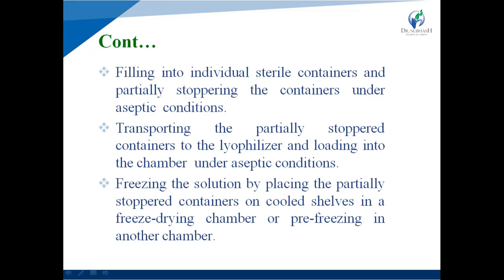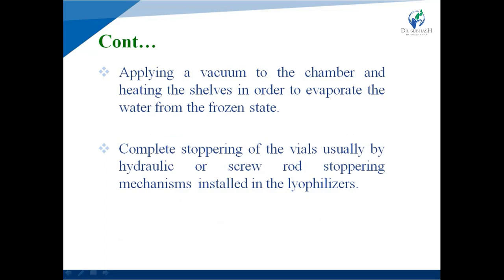Next, freezing the solution by placing the partially stoppered containers on cold shelves in a freeze-drying chamber, or pre-freezing in another chamber. Then, applying a vacuum to the chamber and heating the shelves in order to evaporate the water from the frozen state — that means heating is applied to evaporate the water from the ice stage.